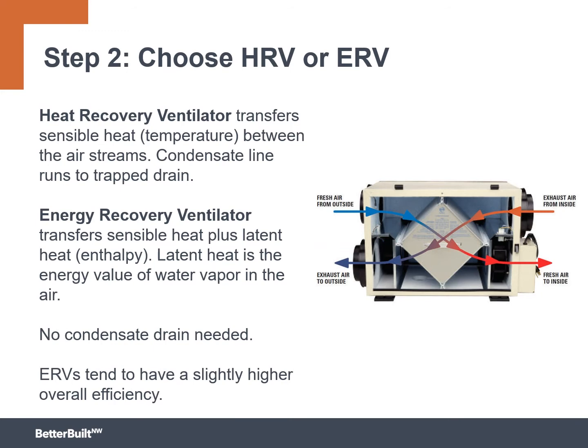The next step in choosing a balanced ventilation strategy is making the decision to go with energy recovery or heat recovery. We've said these terms a couple of times, but we haven't really gone into that yet. So let's talk a little more about the difference between these two. A heat recovery ventilator, or HRV, transfers what is referred to as sensible heat, or just temperature, between the two airstreams. The air being exhausted out and the air being supplied in go through a core. The two airstreams don't actually touch. They go through a heat exchanger, which allows some of that heat to be transferred to the incoming air. A condensate line, because condensation is likely to happen in a scenario like this, is involved, and it needs to be run to a trapped drain.